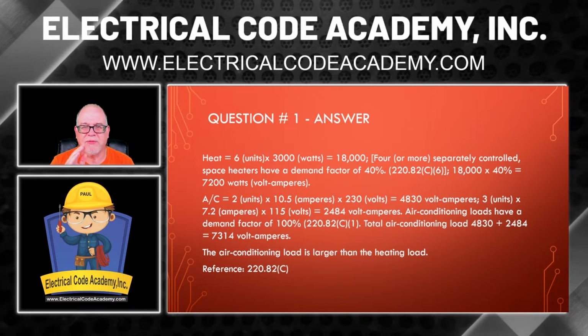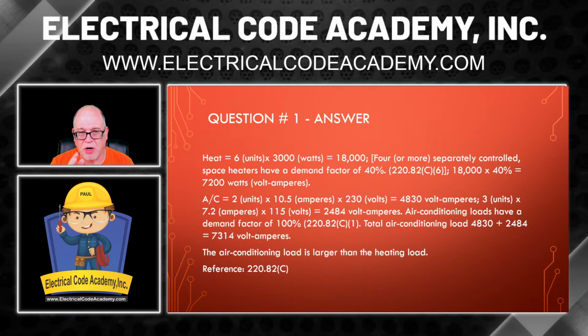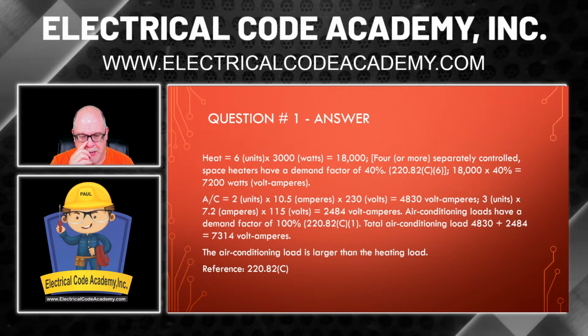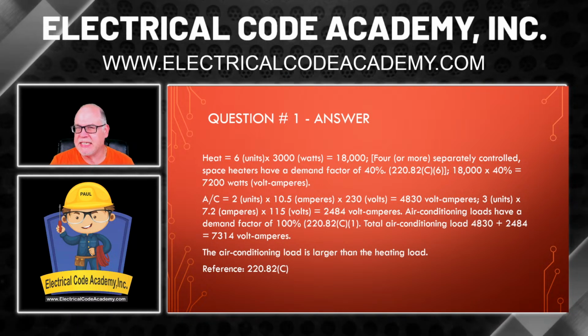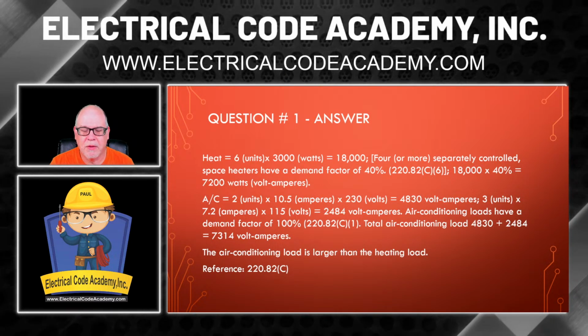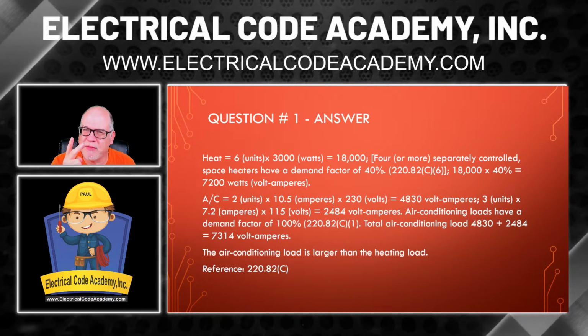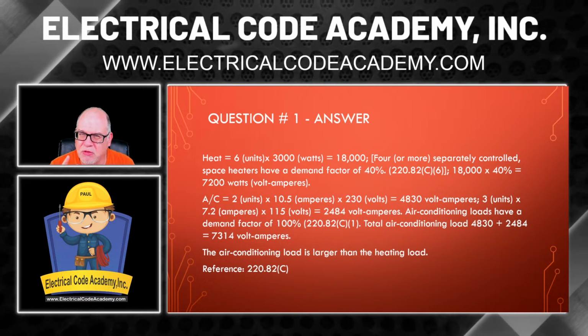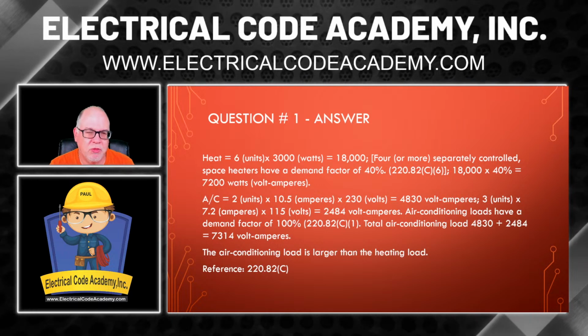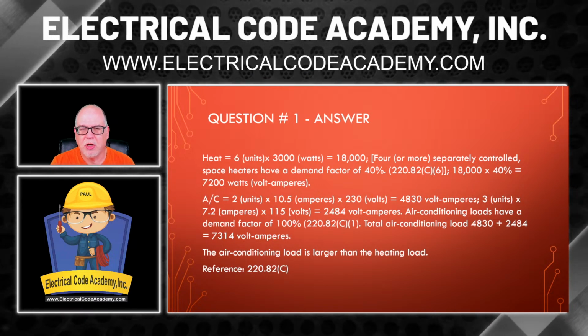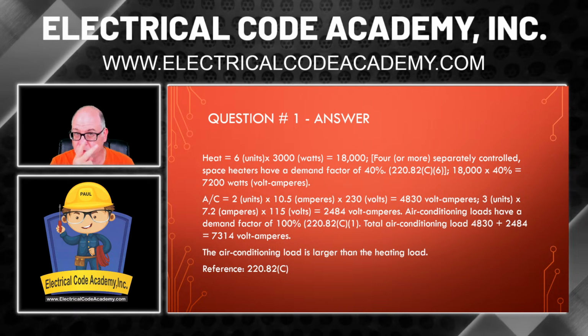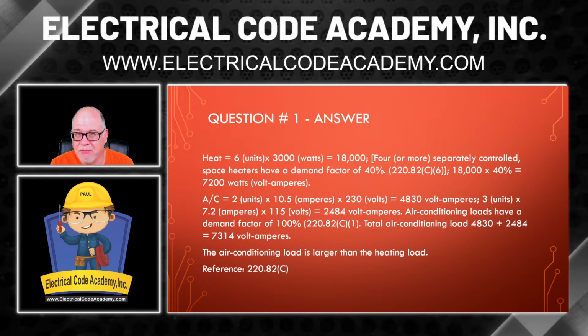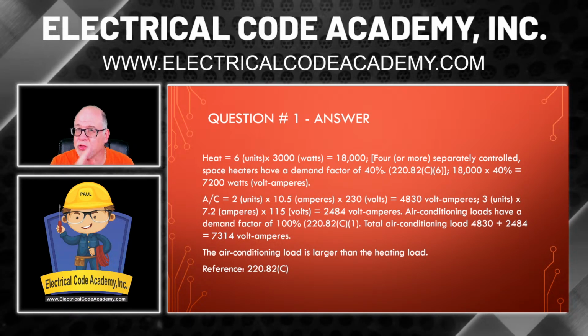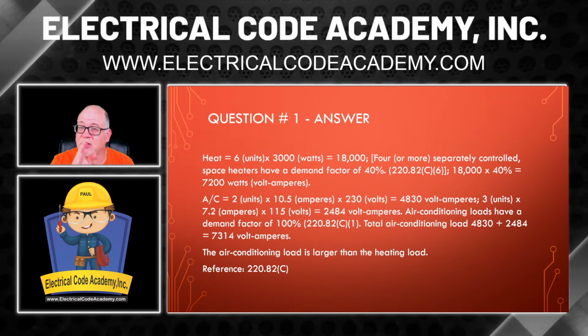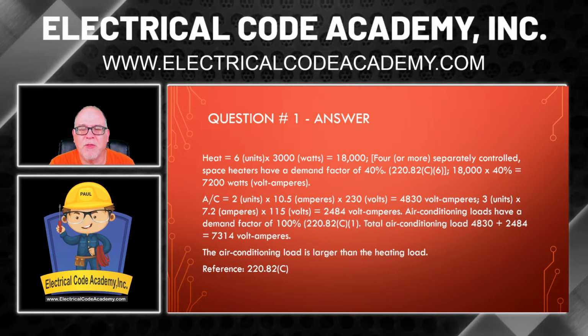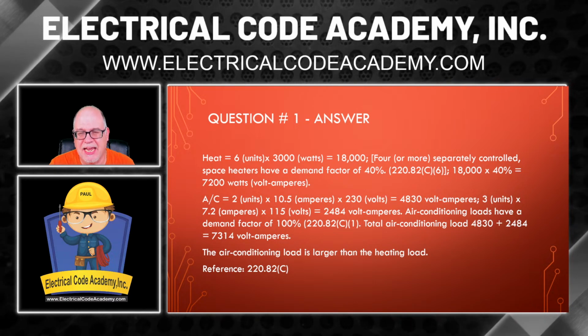Now let's look at that AC, because we know that we've done the heat already, and 7,200 is what we're working with for the heat. Is that going to be greater than the AC? Well, that's what you got to work out. So remember we had 2 of them at 10.5 amps each, and we had 3 of them at 7.2 amps. So easy math. 2, because there's 2 of them, times 10.5 times 230 volts. Remember, use the voltage that's given in the question. That's going to give us 4,830 VA.